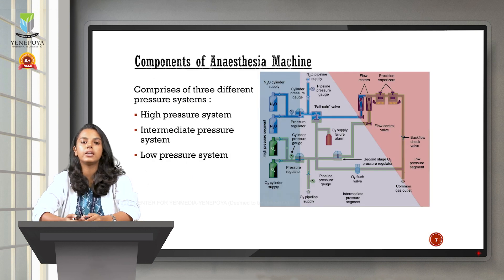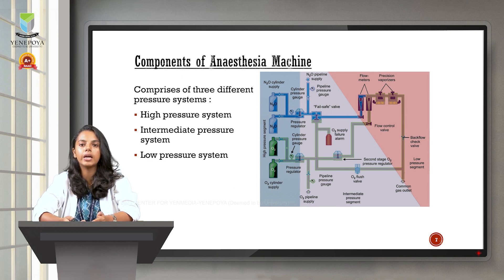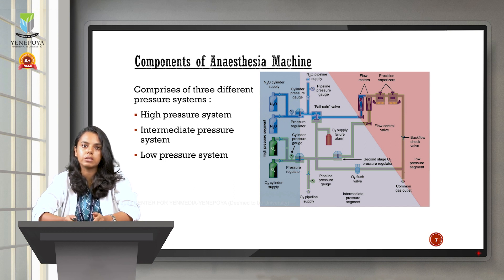Coming to the components of the anesthesia machine — the machine is made up of various parts including tubings, valves, and cylinders. All these components are divided into three pressure systems based on the pressure of the gas inside them: the high pressure system, intermediate pressure system, and low pressure system.